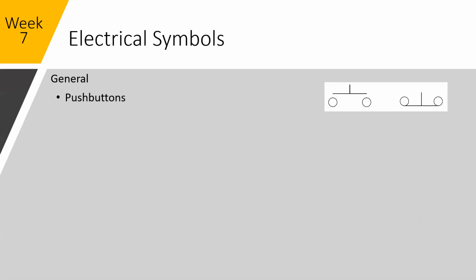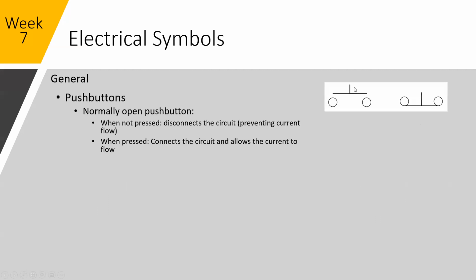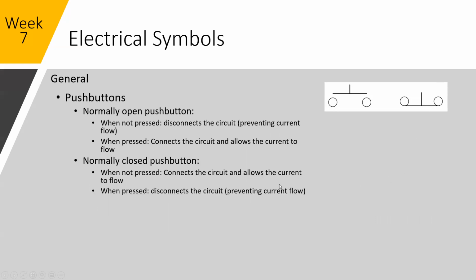We've covered these already. These are push buttons. So we've got a normally open, a normally closed push button. So a normally open push button, when not pressed, is a disconnected circuit. The normally closed push button, when not pressed, is a connected circuit. When you press them, they will either open or close their circuit respectively. Normally closed, normally for stop buttons or fault signals. Well, these are buttons, so not fault signals, but these are stop buttons. These ones would be start buttons, typically.